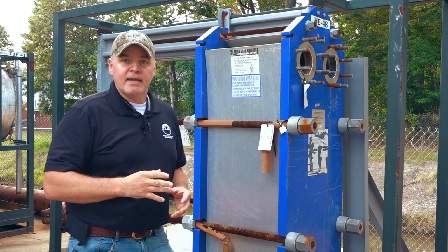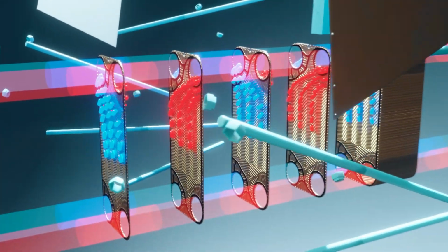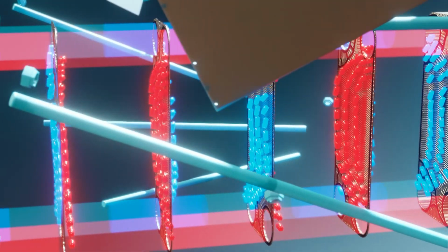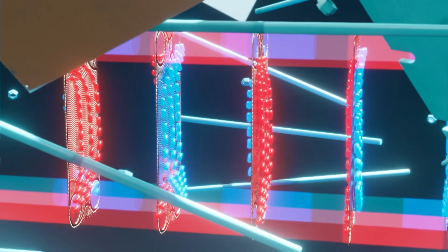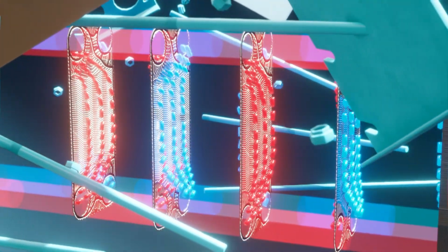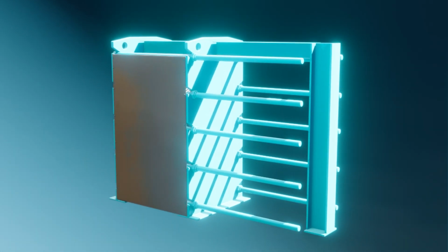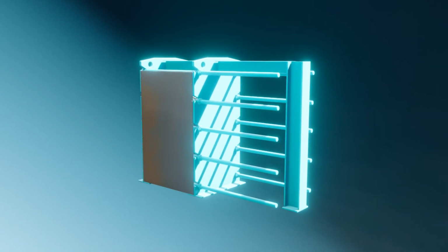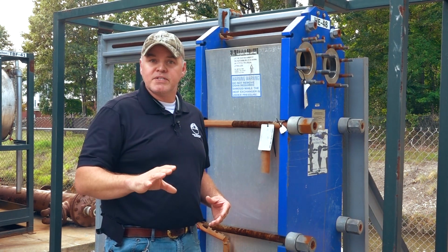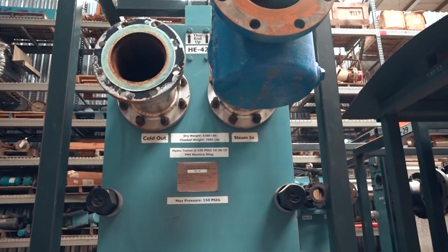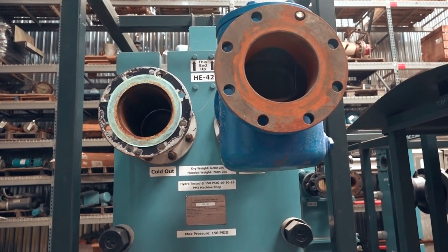The flow-through design, this cold side would be where our glycerin is flowing, and the hot water would be simultaneously being passed through on the hot side. As the flow continues, an exchange of BTUs from the hot to cold sides will occur and bring that glycerin up to the temperature without ever contaminating it. So as the flow continues, the glycerin will then be pumped through and on into the remainder of the process while the hot water continues through the closed loop and is then reheated, and the cycle will just continue.